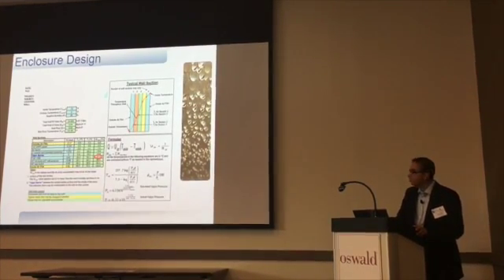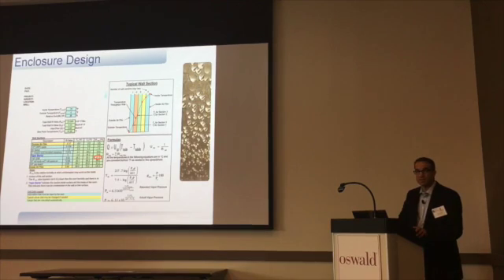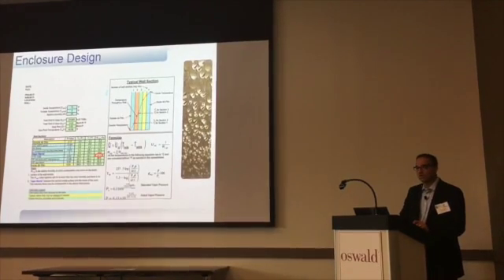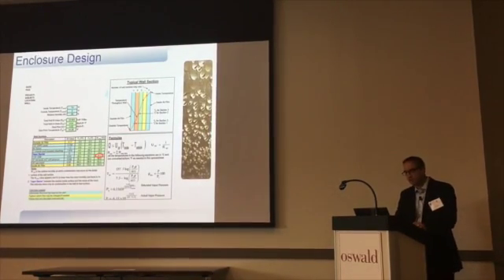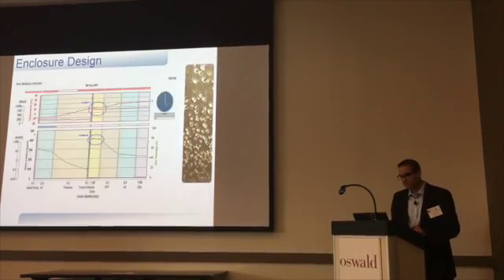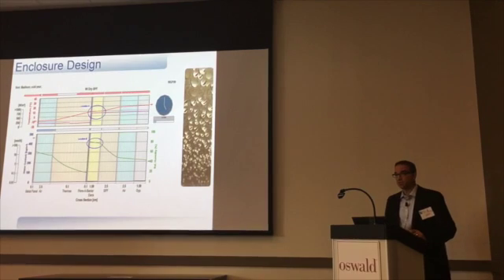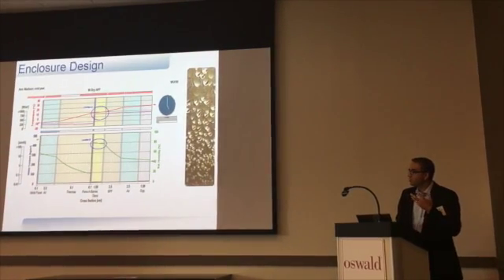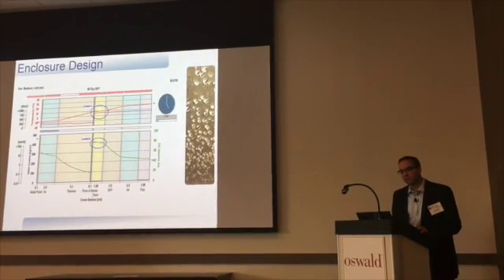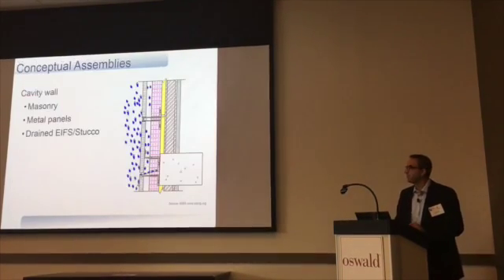We have lots of tools as an industry to determine where the dew point is and what kind of risk we might have for condensation. Why do we care about condensation? That's one of the foundations of mold growth, and also the inability to control the environment on the inside. There are two-dimensional spreadsheet-based analyses, and programs such as WUFI. As industry professionals, you have a pretty good feel for where that dew point is going to be most of the year, and then you can overlay the drying capacity to get a sense for where you are.